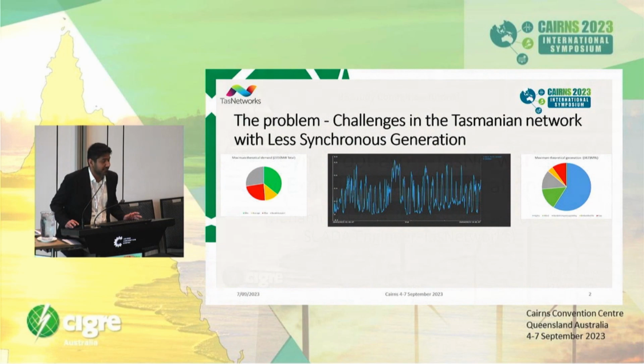So there has been a challenge for everybody probably with the increase of IBRs, inverter-based resources. We have been having non-synchronous penetration in our network. This is one of the snapshots from PMU data, which is telling us 80% of the generation in TAS Networks is non-synchronous penetration. So if it's a good windy day and we are using wind farms and lesser load is required, and maybe we have Basslink from Victoria providing us 500 megawatts, we probably don't need any synchronous generation to help run our network. But what it does is it decreases the inertia of the system, and yes, it impacts the system stability. Now this is one of the major issues which we'll probably continue to face with the increase of PV to be embedded in our network as well in future.